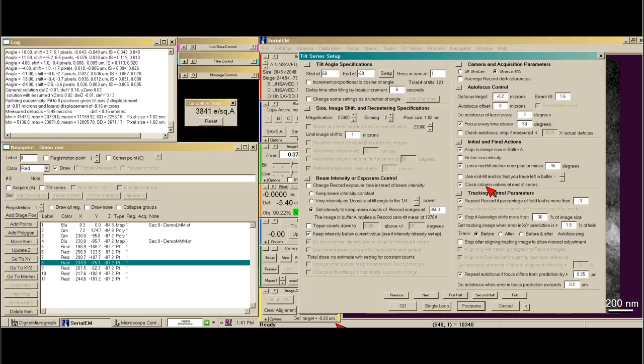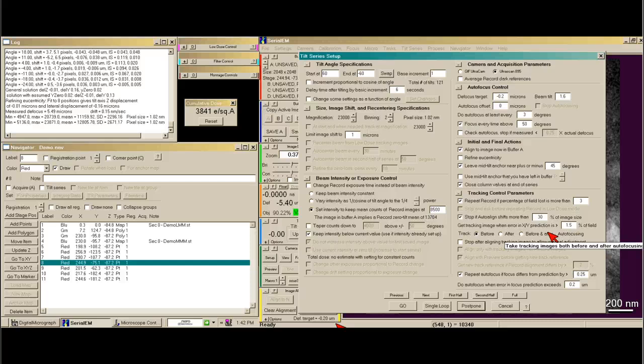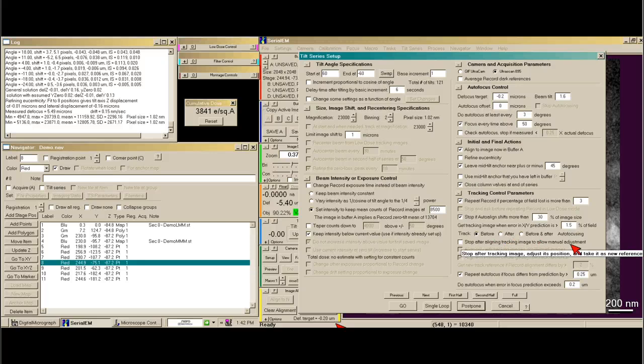Also, at the end of the tilt series, if you know you're not going to be in the room, it's a good safety check to just close the column valves. When you're tracking, you can allow it to take a new record image if you've moved more than 3% away. Also, if you get some funny lurch in your CompuStage that is more than 30% of the image size, it will stop and ask you if this is correct or not, and you have options to fix for that. You can track either before, after, or both before and after autofocusing. Most of these parameters are all defaults and you really don't have to change them much.